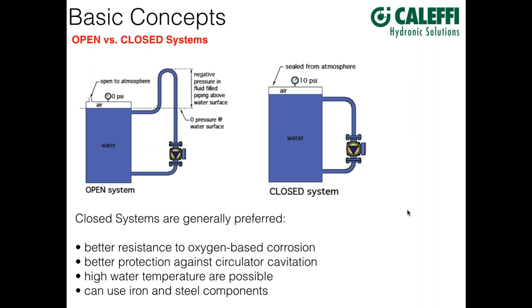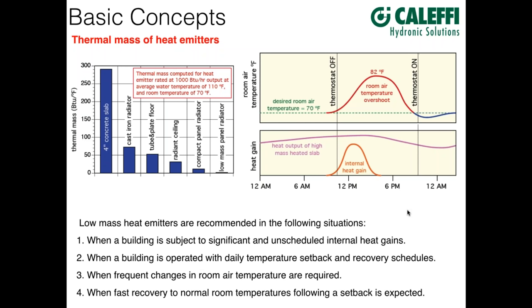Another important concept when putting together a system is thinking about the thermal mass of the heat emitters. There's a huge range of thermal mass. A concrete slab with tubing is going to have a much higher mass than, for example, a compact steel panel rad or a baseboard — actually about 100 times more thermal mass than some of the very low mass convective panels available today.